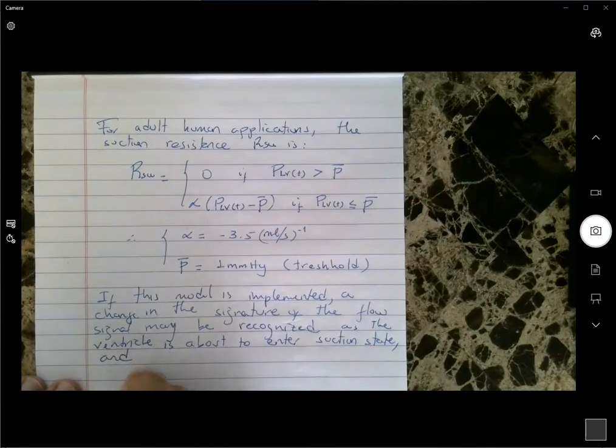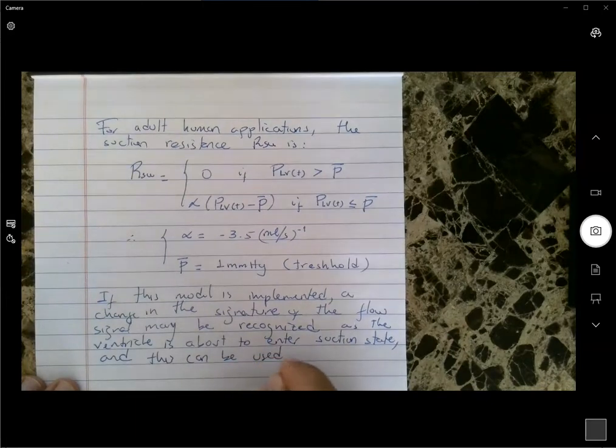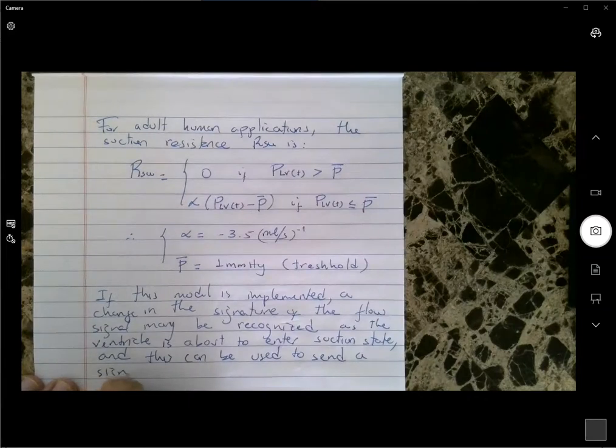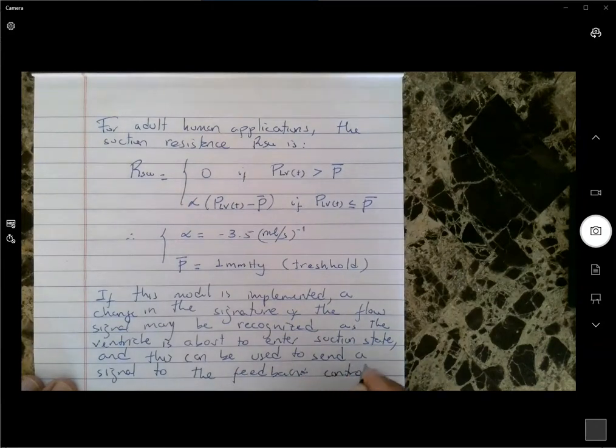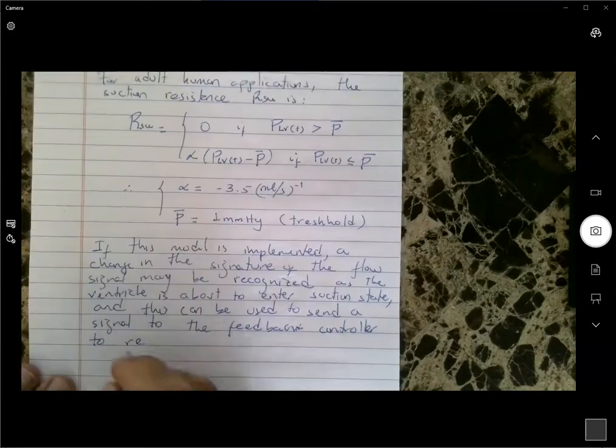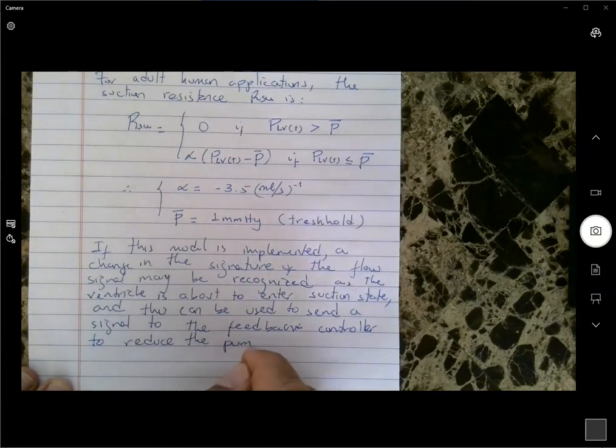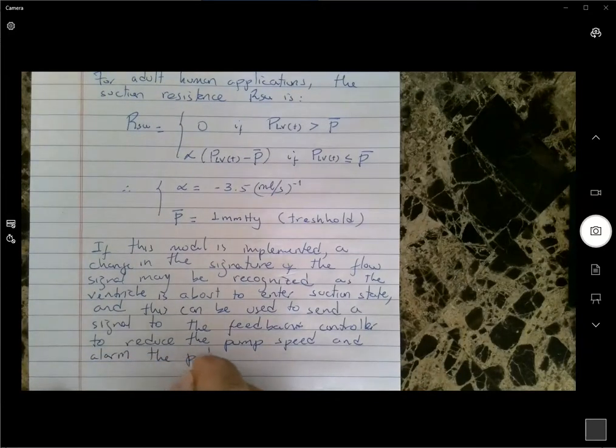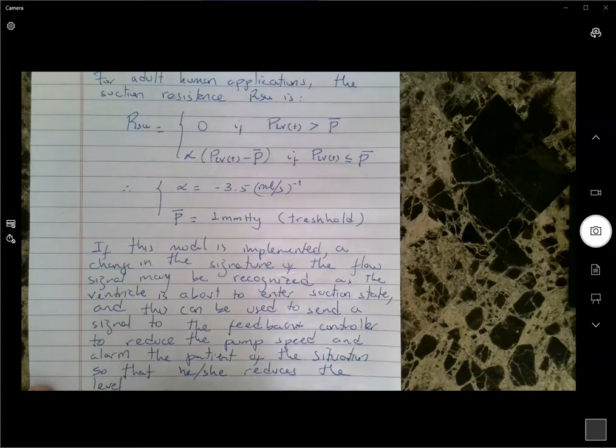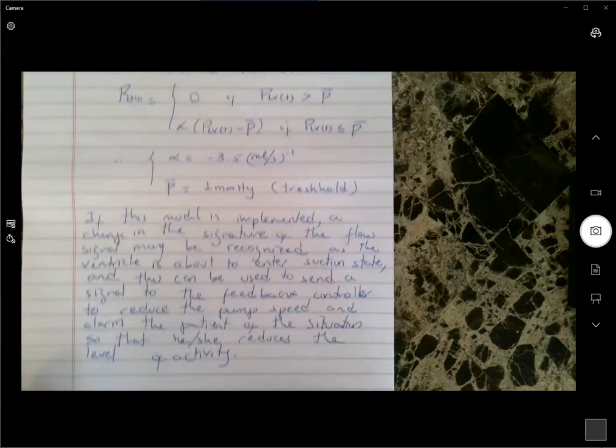And this can be used to send a signal to the feedback controller to reduce the pump speed, and alarm the patient of the situation so that he or she reduces the level of activity, thereby reducing the physiological demand.